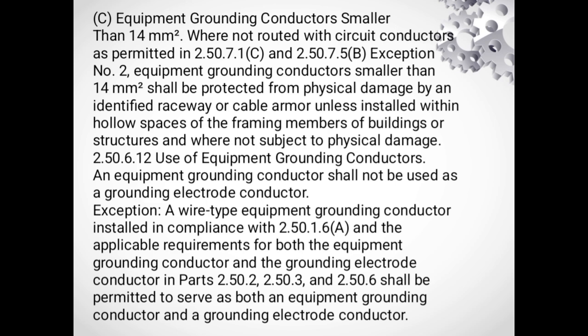2.50.6.12 Use of equipment grounding conductor. An equipment grounding conductor shall not be used as a grounding electrode conductor. Exception: A wire type equipment grounding conductor installed in compliance with 2.50.1.6a and the applicable requirements for both the equipment grounding conductor and the grounding electrode conductor in parts 2.50.2 and 2.50.6 shall be permitted to serve as both an equipment grounding conductor and grounding electrode conductor.